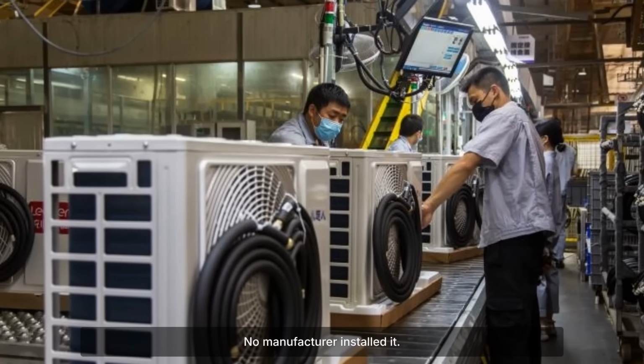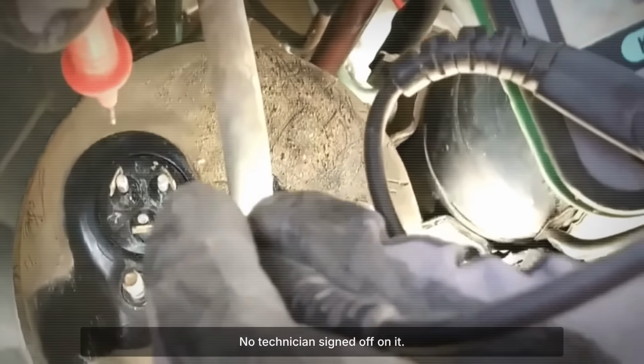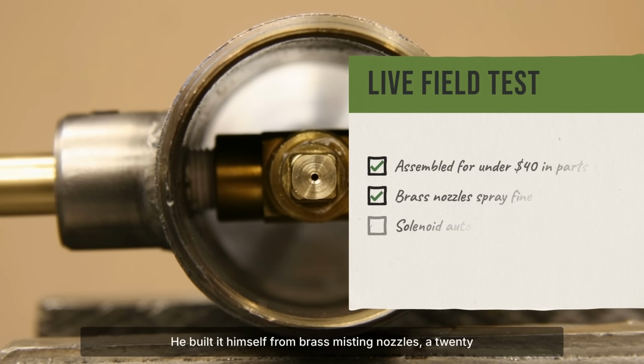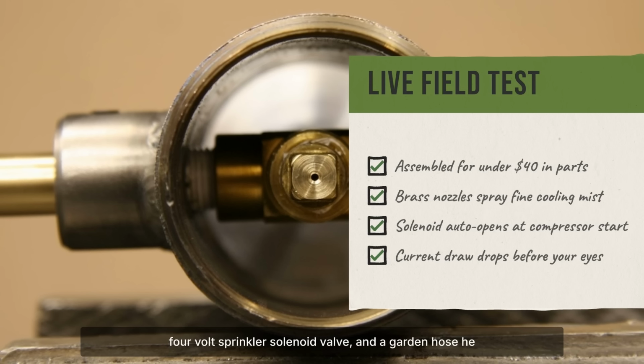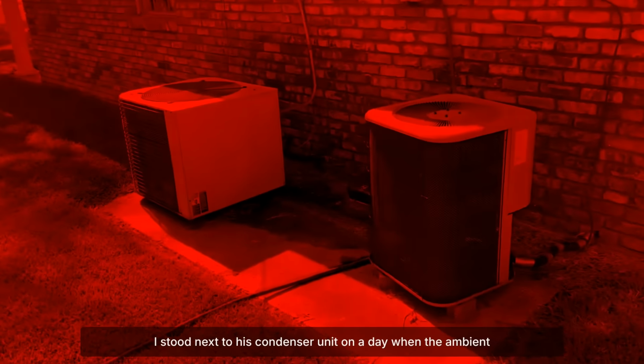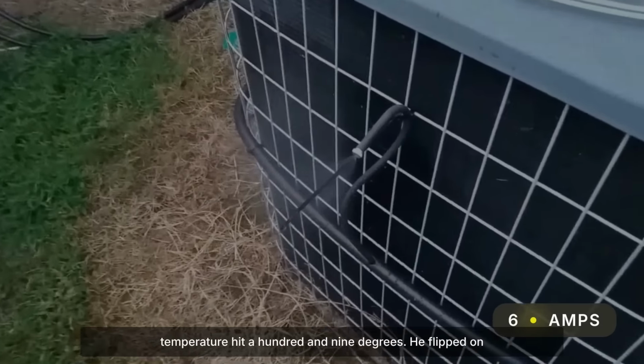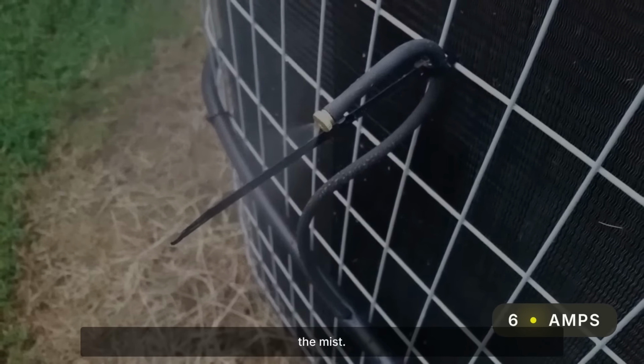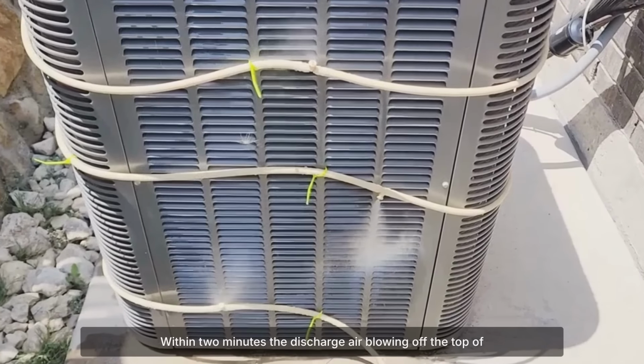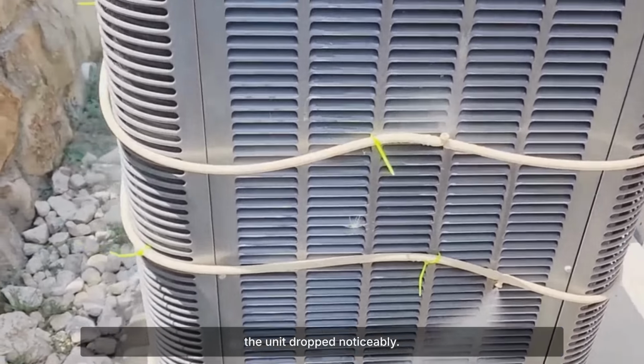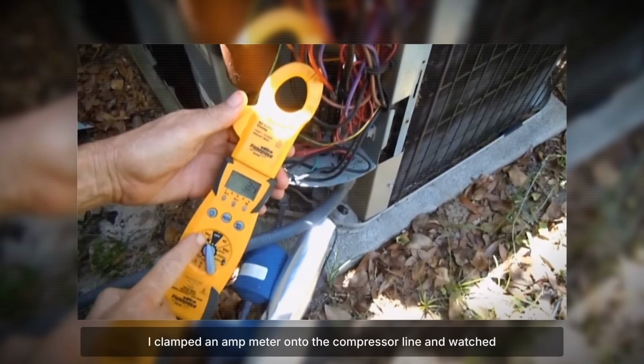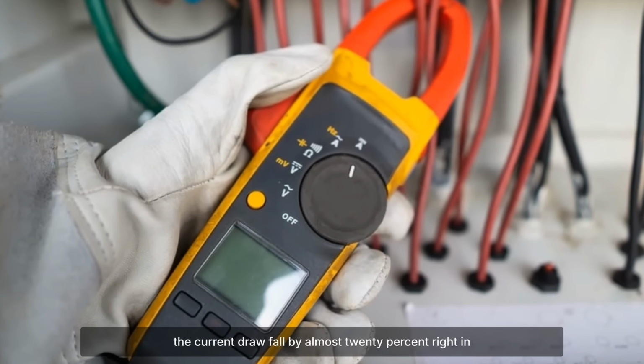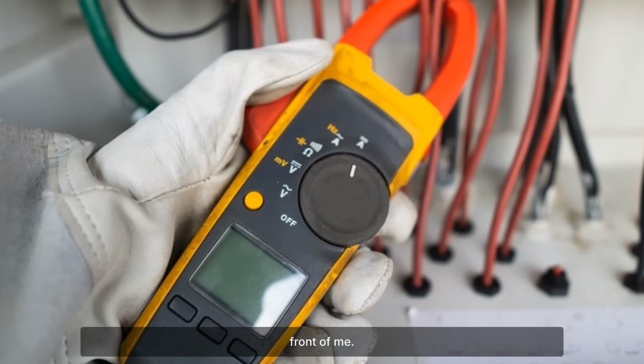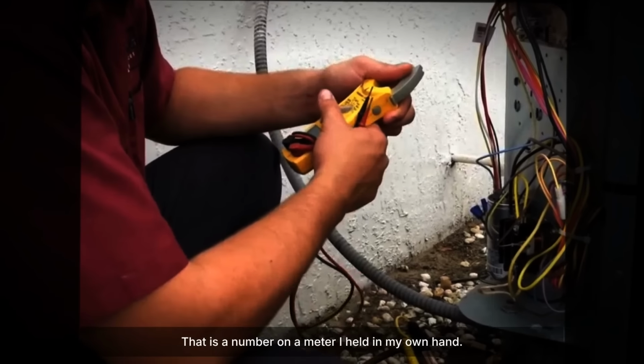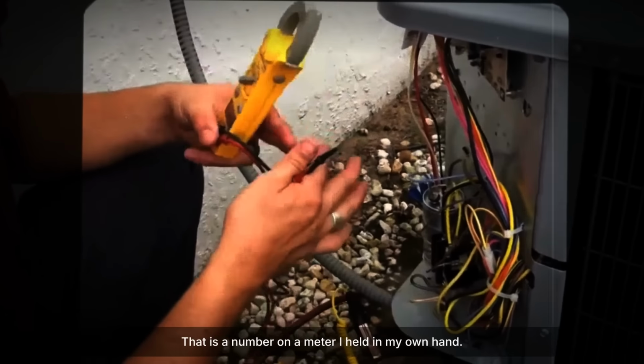No manufacturer installed it. No technician signed off on it. He built it himself from brass misting nozzles, a 24-volt sprinkler solenoid valve, and a garden hose he already owned. I stood next to his condenser unit on a day when the ambient temperature hit 109 degrees. He flipped on the mist. Within 2 minutes, the discharge air blowing off the top of the unit dropped noticeably. I clamped an amp meter onto the compressor line and watched the current draw fall by almost 20% right in front of me. That is not a theory. That is a number on a meter I held in my own hand.